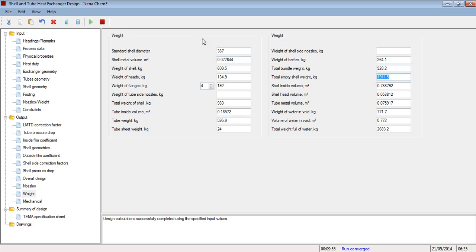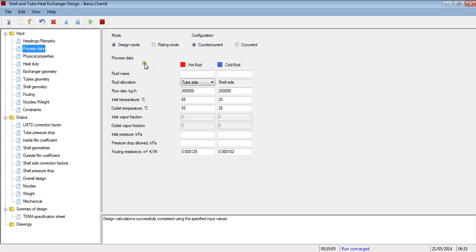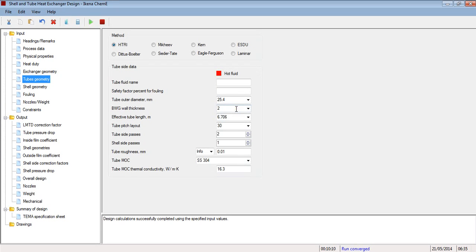Okay, so as I mentioned previously, heat exchanger design is a complicated process. Some of the common design variables include the configuration, baffle geometries, baffle spacing, tube IDs, tube diameters, tube lengths, number of shell and tube side passes. As you have noticed, when we increase the number of passes, the heat transfer coefficient increased. So a designer will need to understand what effects these can have and what variables can be forced and to what extent.